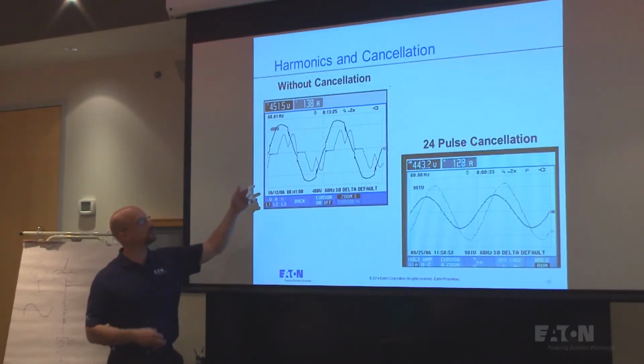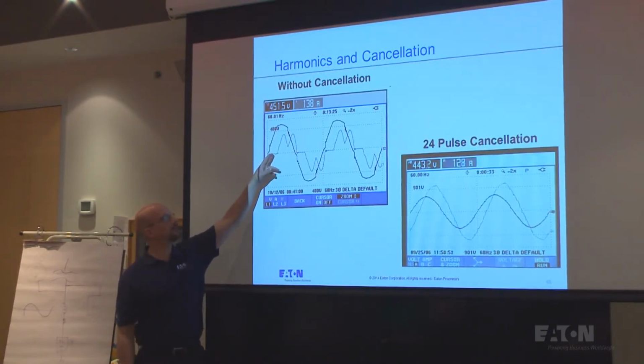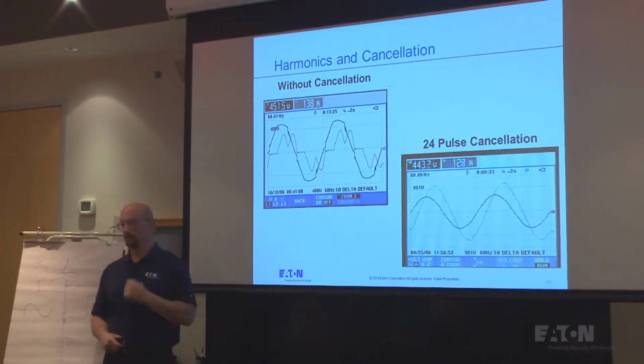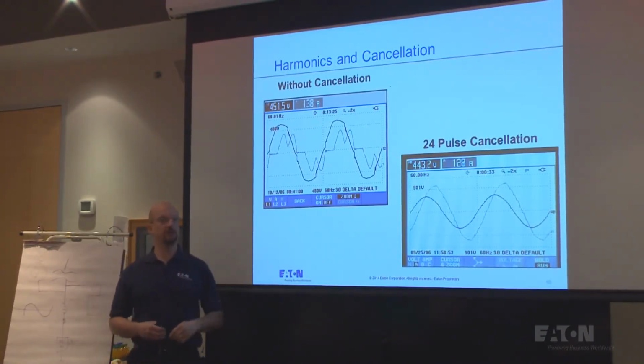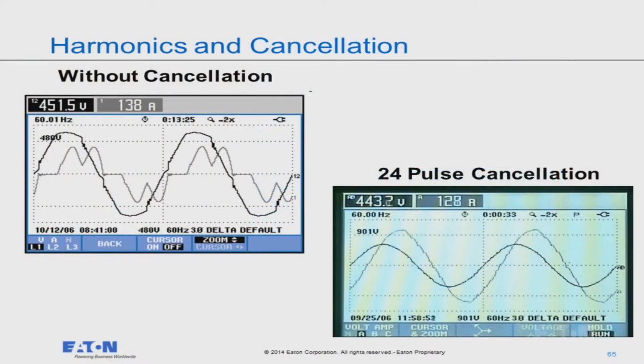Here's phase shifting with 24 pulse. So I take 4 drives and I phase shift 6 pulse drives, 0, 15, minus 15, and 30, and I end up with waveforms that look like that. It's almost perfectly linear. If I have that on my system, I don't need to worry about harmonics anymore. So it goes back to what systems were designed for 35 years ago, right? They were designed for 60 hertz voltage and current, and that's what you're going to get. Very, very little harmonic current.